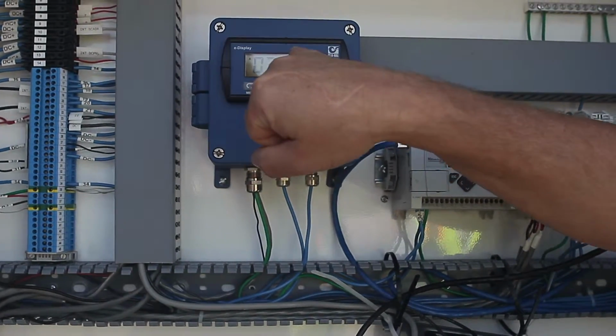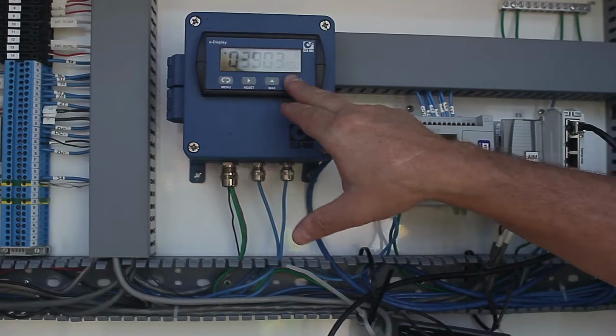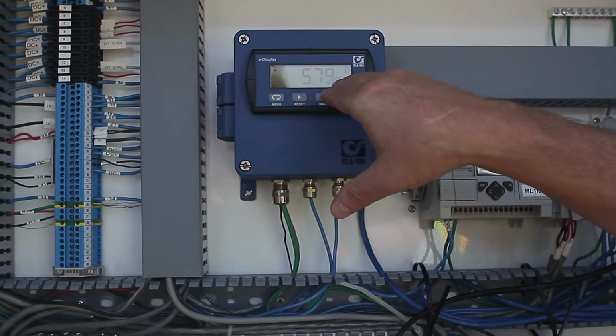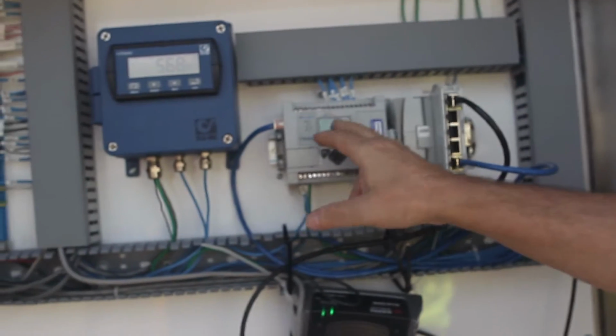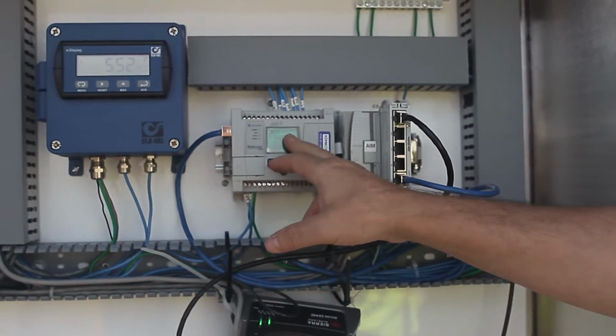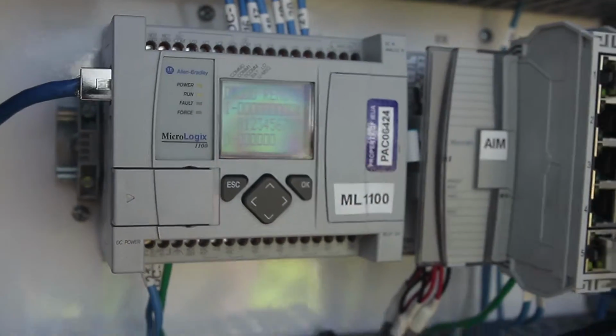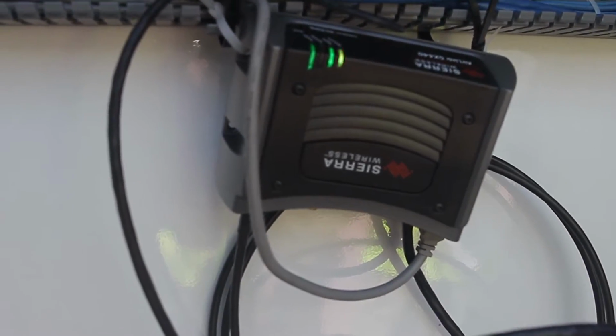We're about 400,000 gallons. Now, I don't know if you can hear it. I'll just toggle back to the rate in million gallons per day. You can hear a little click. There is a pulse output from the meter itself to a little relay that clicks just shy of every 10 seconds. Every pulse is 500 gallons. That is coming into the telemetry PLC that they're remotely monitoring and totalizing through SCADA. And then they have the radio here being wired up to remotely read all of this information. And as I understand, they have upstream and downstream pressure coming into the panel here.